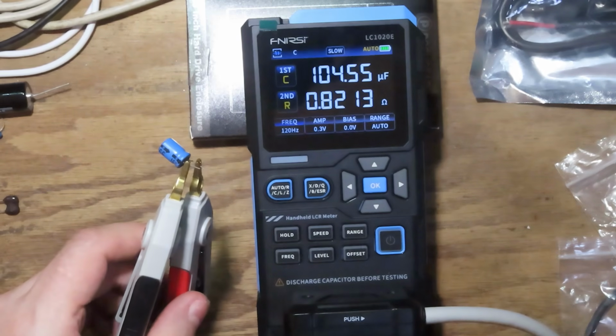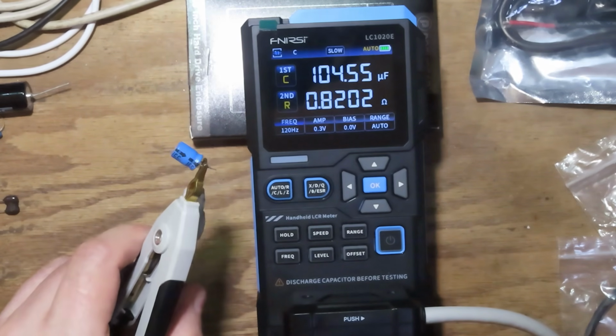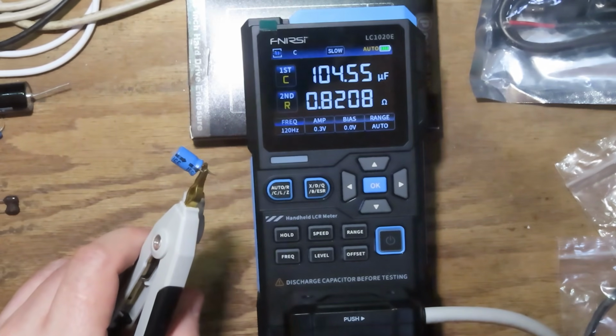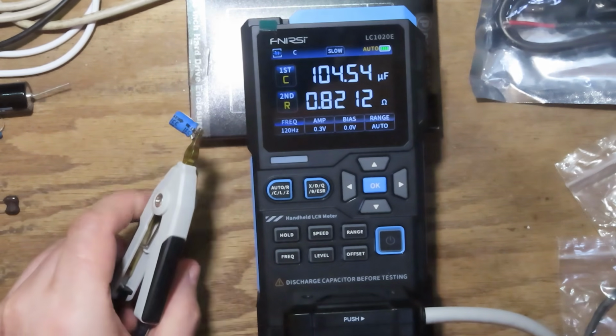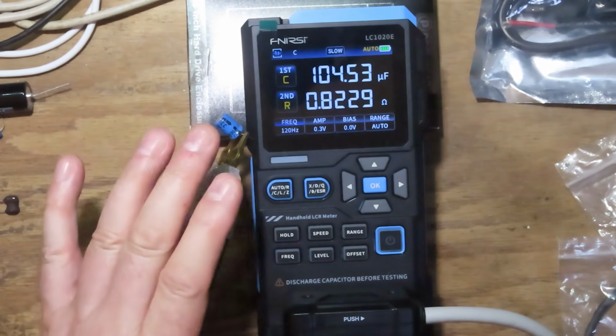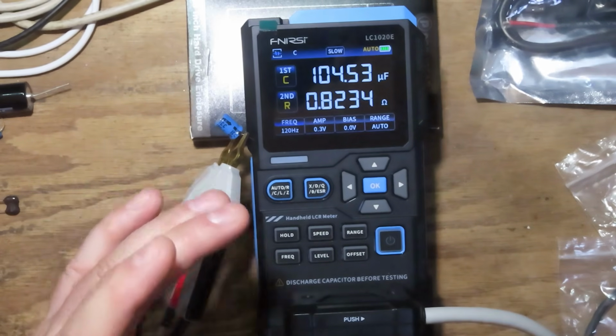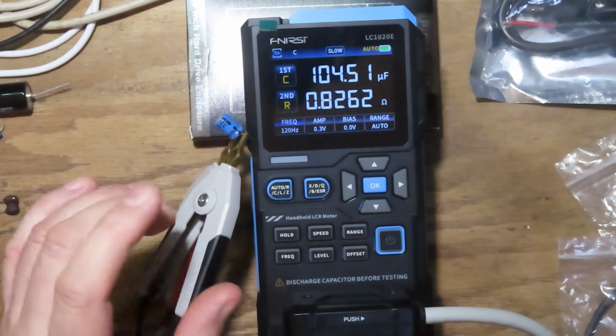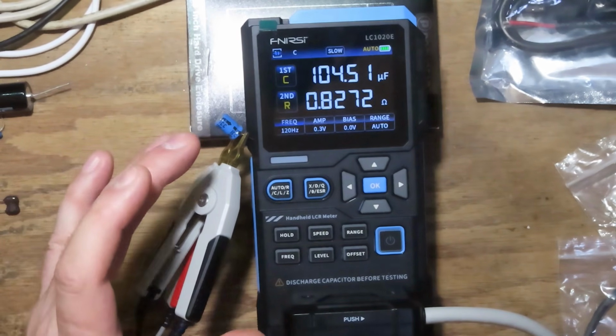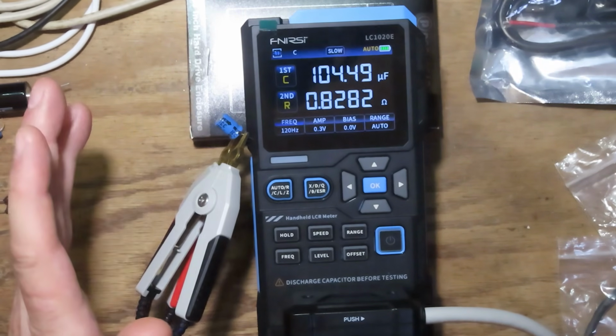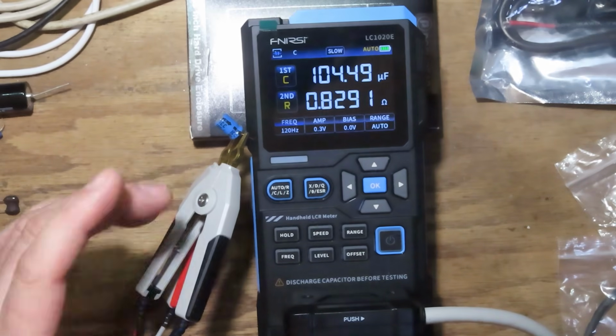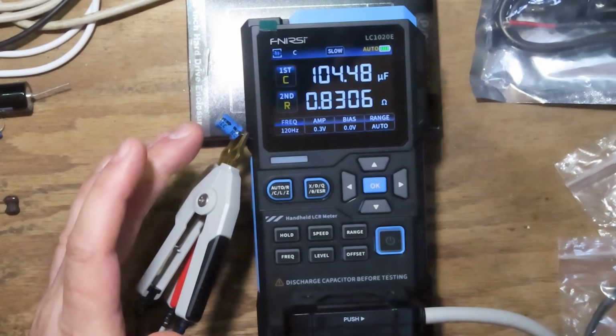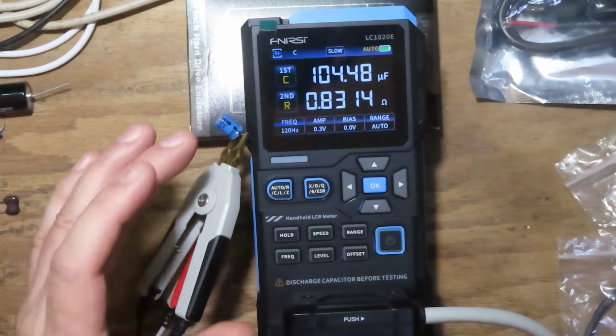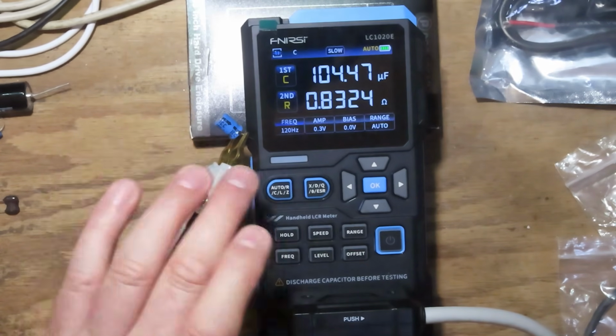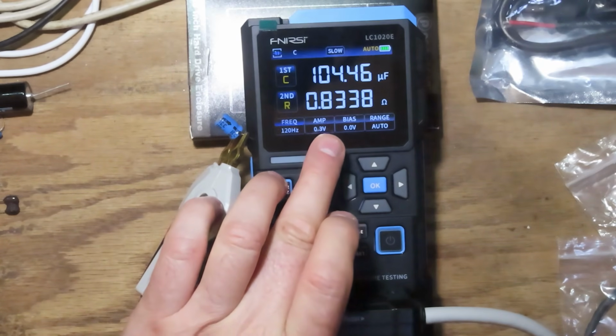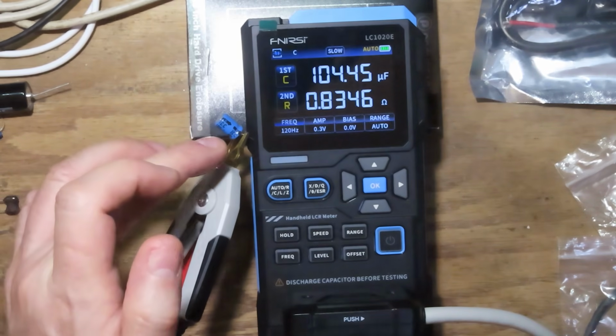And we're seeing 104 microfarads, which is respectable for this old of a capacitor, and an ESR of 0.82 ohms. Now, ESR, equivalent series resistance — as an electrolytic capacitor ages, it begins to develop higher resistance to AC current. A perfect capacitor should be 0 ohms to AC. It should pass AC completely through it within its frequency band or range. But as a capacitor ages, it'll develop a resistance, and if it's a filter capacitor in a power supply, it can become a load.